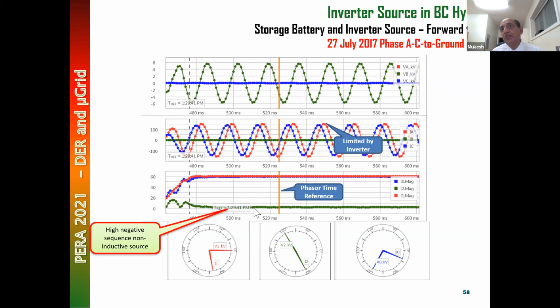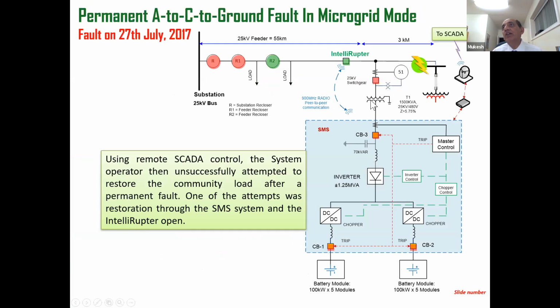And this is what's showing you positive sequence current. And this is a zero sequence current. Red is a zero sequence current. And this is a negative sequence current. We see a lot of zero sequence current because, remember I showed you a transformer, a delta transformer. This is a Y, this is a delta here. Delta is a zero sequence filter. And if there's a ground fault here, you see, the delta transformer is a zero sequence current source. If there's a ground fault here, it supplies a lot of zero sequence current.